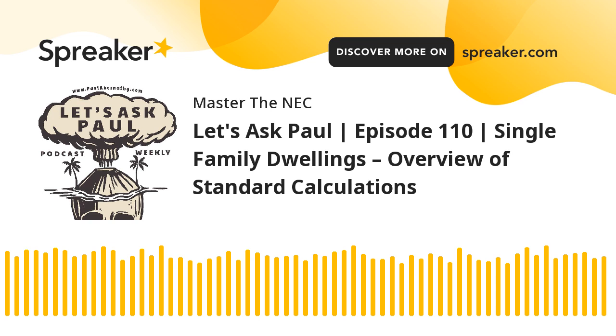And so that's 220.52(A). If you look at 220.52(A), here's what it says. It says small appliance load circuit. In each dwelling unit, the load shall be calculated at 1500 VA for each 2-wire small appliance branch circuit as covered in 210.11(C)(1). Okay, that's the one that tells you got to have at least 2. All right, and so that's the first part that we need to take into consideration.